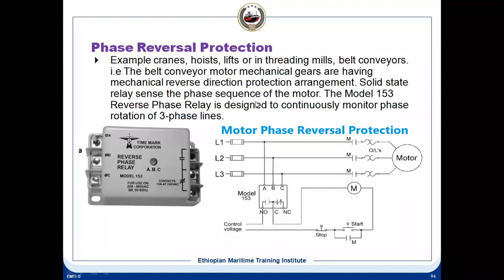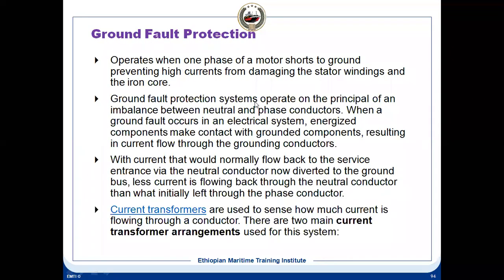Phase reversal protection. Then the next one is ground fault protection. Ground fault protection operates when one phase of the motor shorts to ground, preventing high currents from damaging the stator windings and the iron core. Ground fault protection operates on the principle of an imbalance between the neutral and phase conductors.